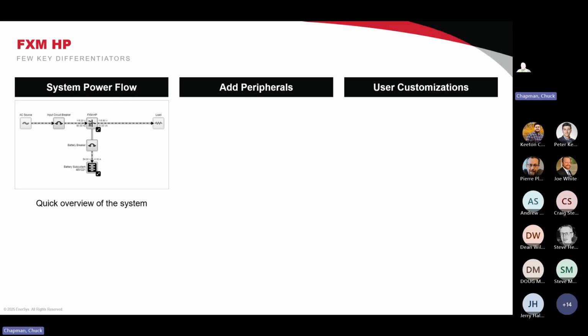It has configuration for its operation. So even though you may see the inverter go into a problem mode, you can diagnose it, maybe fix the electrical system. But if it's unfixable, you can change some of the ways the FXM HP operates. You can tell it to wait longer to reconnect, or tell it to qualify the line as a generator rather than an AC power line, so it's a little more accepting of frequency changes or something that might be completely rejected in normal mode.